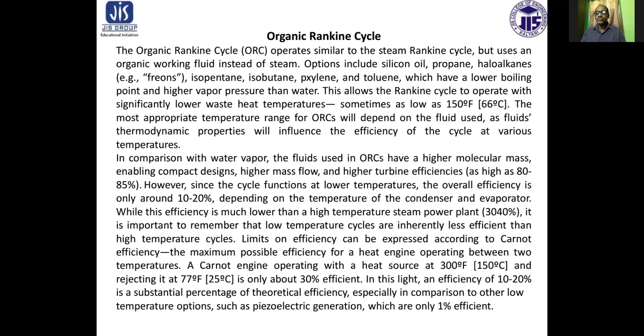Although high capital cost is required for both these cases, industrialists may choose the organic Rankine cycle. But the maintenance of this cycle needs to be very careful, because the working fluids are silicon oil, halocarbons, that is freon, isopentane, isobutane, etc. If leakage takes place, it will be harmful to the atmosphere and to the workers in the plant. So safety is first. If we go for the organic Rankine cycle, one must be sure that sufficient technology is used so that the chance of leakage, the environmental impact and the health impact on workers are kept in mind.